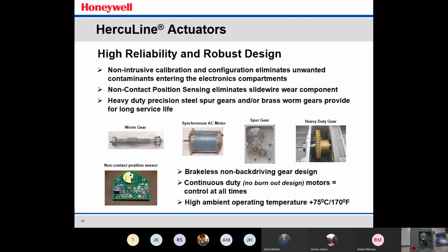When we talk about the Herculine reliability and robust design, in the middle of this slide here, we got the worm gear. This worm gear is used both on the Herculine 2000 as well as the 10260. And this worm gear here offers a self-locking mechanism by using this arrangement on the spindle. These spindles are connected directly from the motor all the way through to the output shaft of the actuator. So what that does is it minimizes any hysteresis because it's connected right to the output shaft. And then also this is what allows that high torque stall. Since it's self-locking with this worm gear, it can handle a lot of stall torque beyond what its rated capacity is, and for very long periods of time.